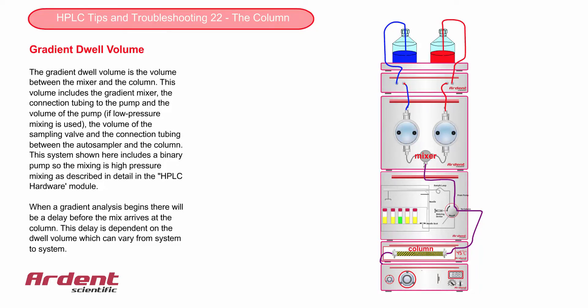The dwell volume is the volume between the mixing chamber of the solvents and the start of the column. This volume is important when doing gradient analysis. For example, if the dwell volume is 1 mL and the flow rate is 1 mL per minute, then it will take 1 minute for the new solvent mix from the mixer to reach the start of the column.